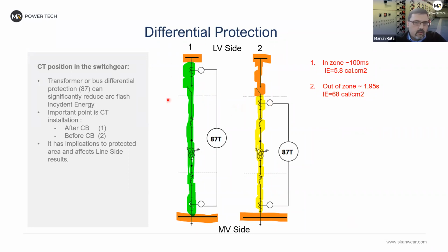So just to focus on the low voltage area, in this case, if we install the CT, let's say, closer to the bus bar, so behind the breaker, everything that happens on the line side or load side of the breaker in this compartment is actually in zone, which will be very fast for tripping. So we expect something like 5.8, below 6 calories, maybe less.